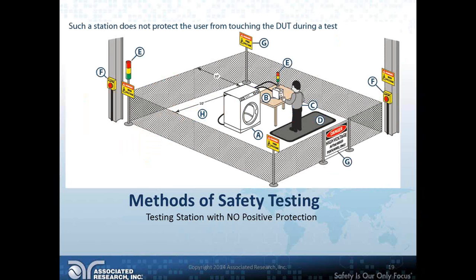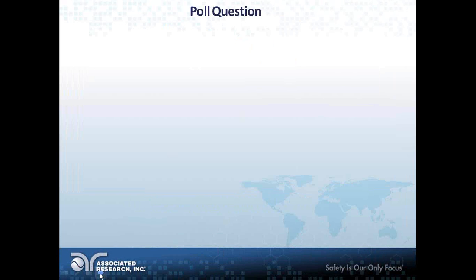This one's especially important. The 10-foot rule would definitely apply here because that is an exposed conductor. If you're running a hipot test on that thing, it's exposed—you can't have unqualified people getting within 10 feet of that. Just a couple of different scenarios I wanted to go over to make sure that's understood.